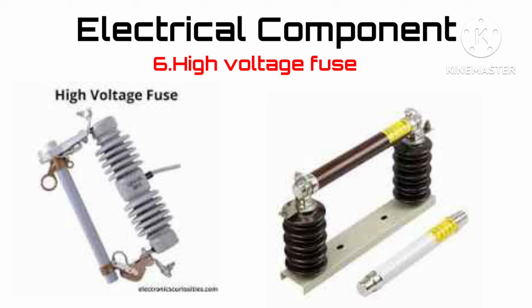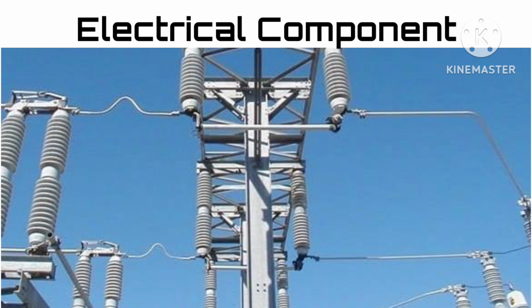The next fuse is the high voltage fuse. This fuse is used in power distribution and power transmission lines. When there is overcurrent and overvoltage in the grid, the fuse bursts and drops down. The high current is not carried forward in the transmission line. This fuse is generally used in transmission lines above 10 kV. It is cheaper than other protection. It vaporizes when an overcurrent scenario happens, and this type of fuse is easy to install. Its other name is drop down fuse.